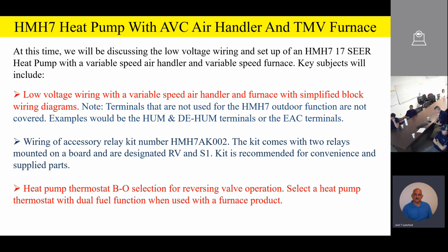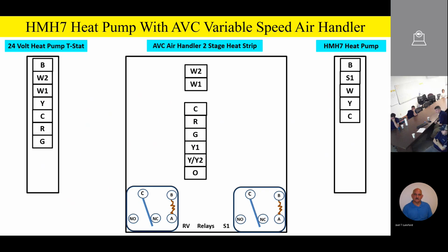Please also remember that on the heat pump thermostat, you have to have that BO selection for reversing valve operation. And if it's on a variable speed furnace, don't forget, it also has to have dual fuel capability if you put it on a furnace. So let's go ahead and start out. We see now that we have 2 relays. Let's start out with the variable speed air handler.